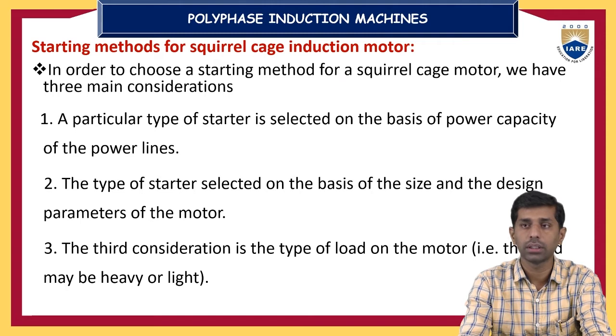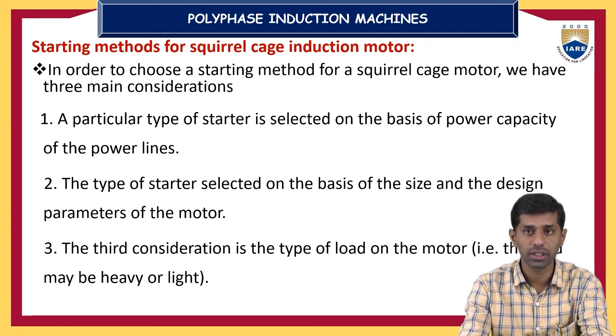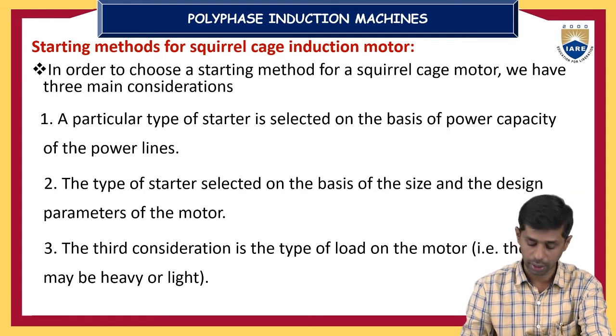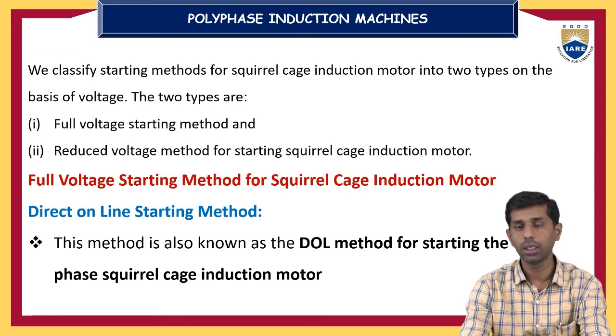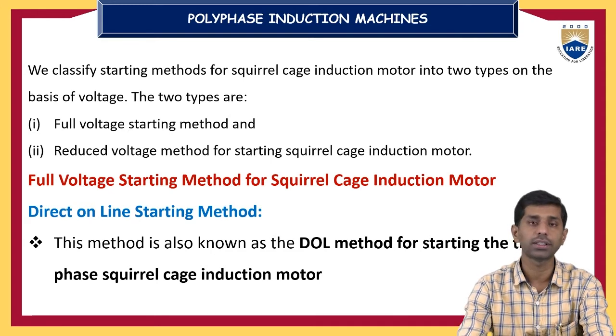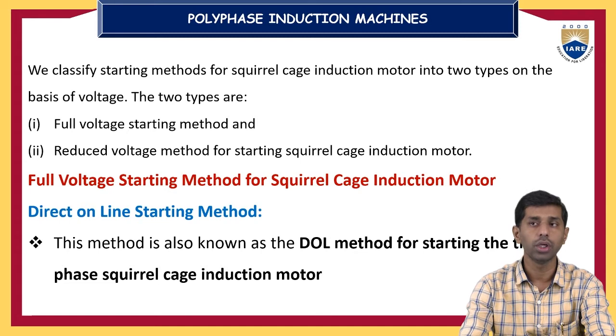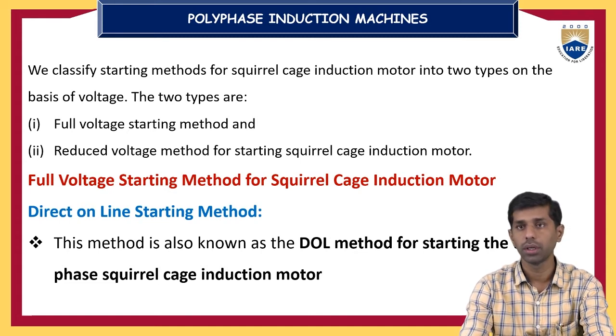So when we select a starter, we should remember the power capacity of the power lines, since a particular type of starter is suitable for that capacity. The type of starter is selected on the basis of the size and the design parameters of the motor. And the third consideration is the type of load connected to the motor, whether it is a light load or a heavy load. According to the above considerations, we can classify the starting methods for a squirrel cage induction motor into two types on the basis of voltage: the full voltage starting method, and the reduced voltage method for starting the squirrel cage induction motor.